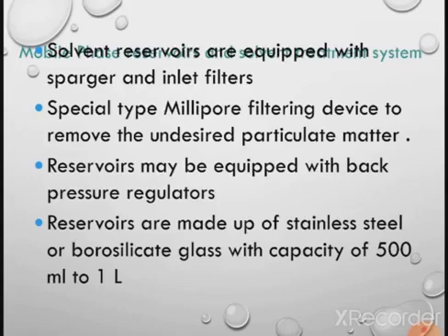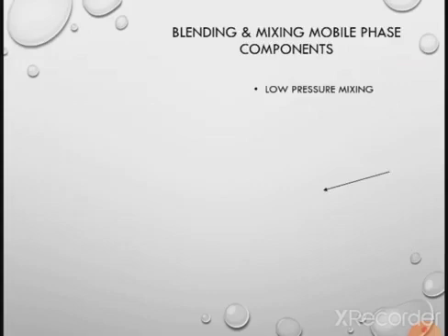Now the next thing is the blending and mixing of the mobile phase components. The blending or mixing of the mobile phase components may be carried out at two stages. First is the low pressure mixing, as we saw earlier, or the high pressure mixing.